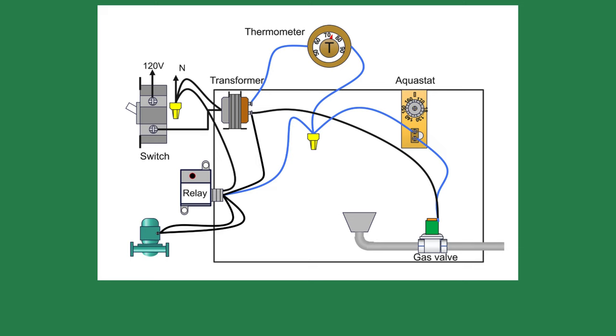A gray relay is attached to the boiler, and two of the wires go to the circulator. The red light is not lit on the relay. What's the first thing you do?